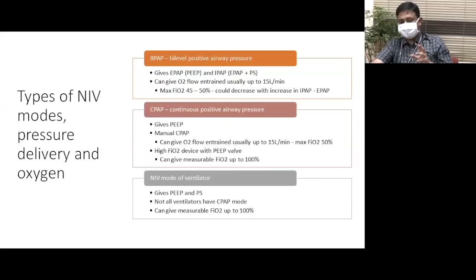Moving on to the NIV mode of the ventilator, this can give the conventional PEEP and the pressure support, and it can give a FiO2 up to 100% because it has an oxygen blender inside the ventilator. But to note, not all ventilators have the CPAP mode, and giving CPAP alone by just decreasing the pressure support to 0 may not work exactly like how the CPAP mode of a ventilator works. So these things need to be kept in mind.